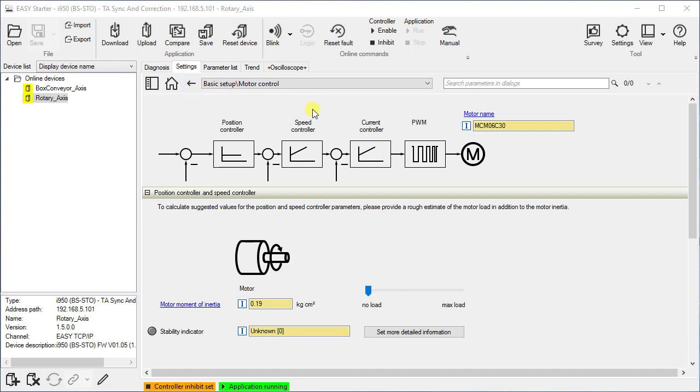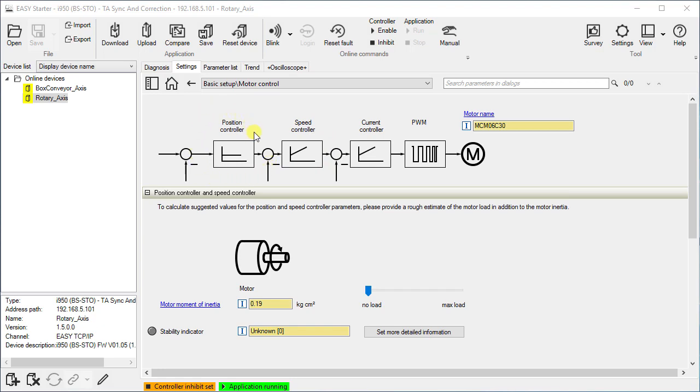The speed controller is automatically set when the motor has been selected from the motor catalog. If no mass inertia of the load is known or set, the automatically calculated settings enable optimum control behavior with an idle motor. In addition, we have a position controller in the servo control, which must be observed when optimizing the drive behavior.